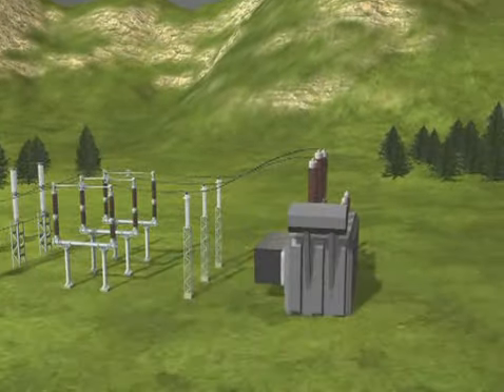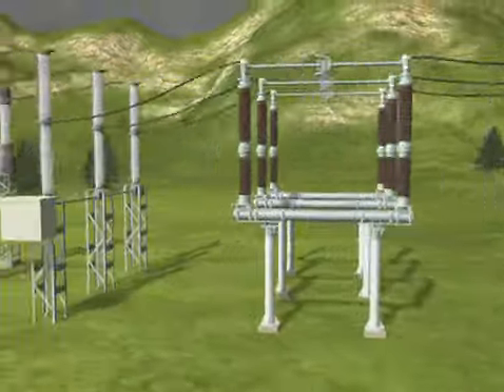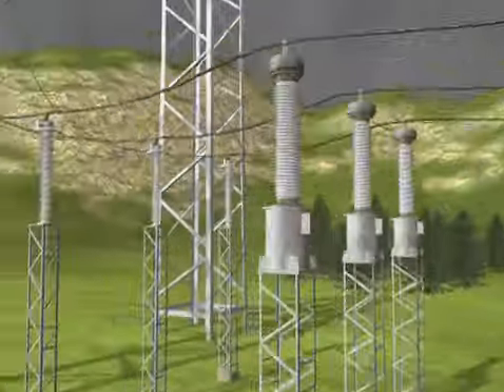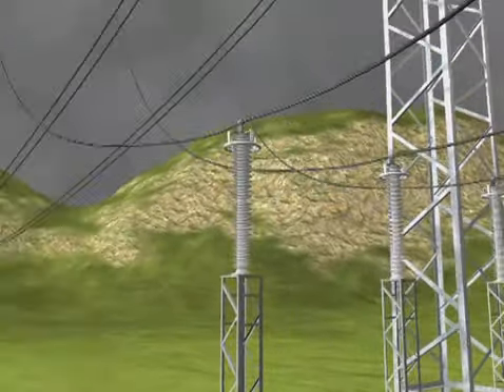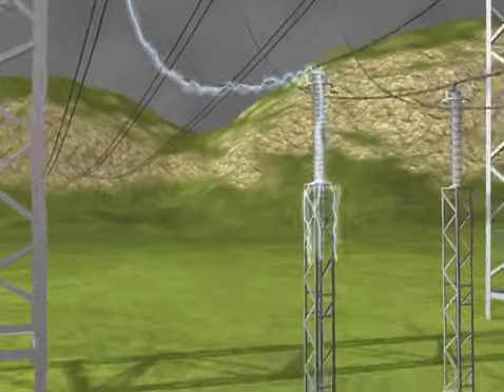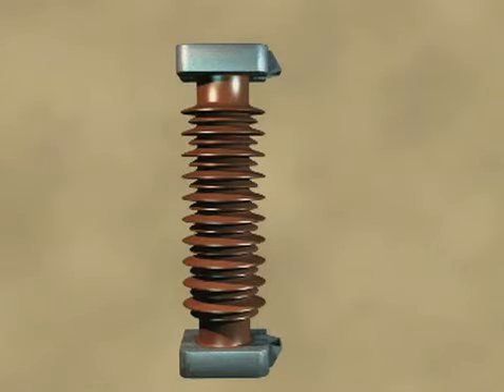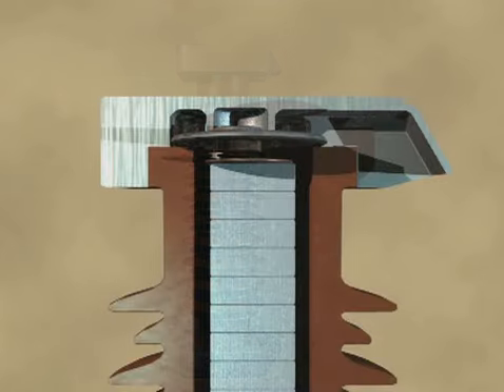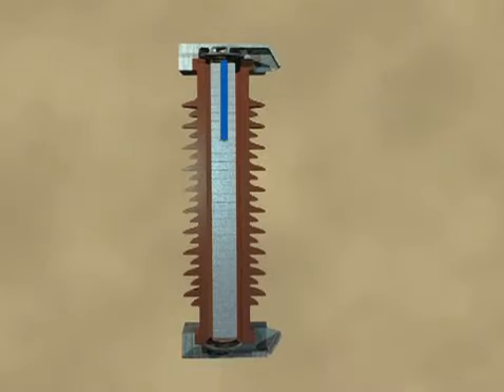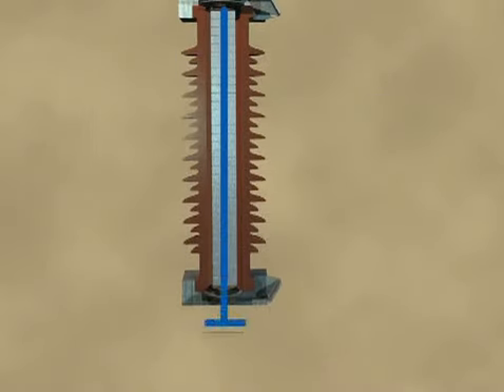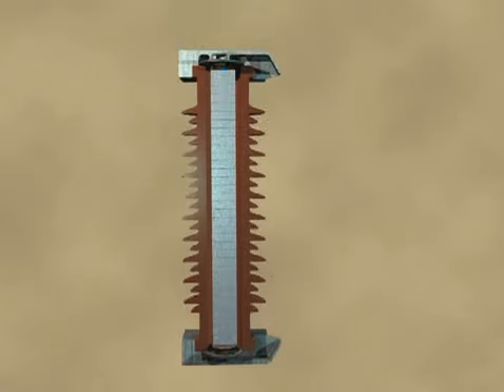The role of the surge arrestor is to protect other components from overvoltages due to lightning or switching in the power system. Under normal conditions, the surge arrestor acts as an insulator. When overvoltages occur due to lightning or switching in the system, the nonlinear characteristics of the metal oxide block cause the overvoltages to be led to Earth through the surge arrestor. Afterwards, the arrestor resumes its previous standby status.